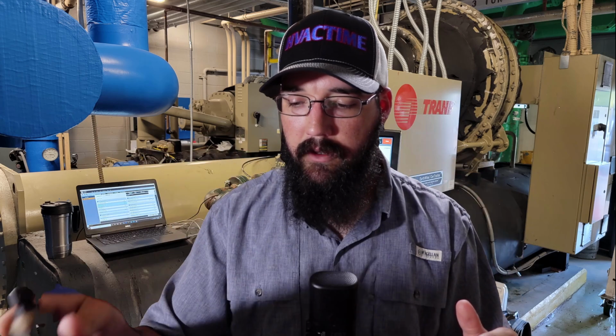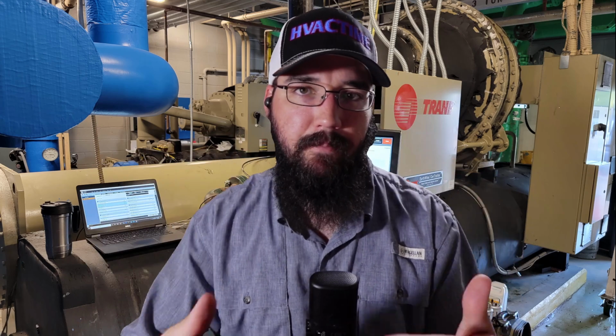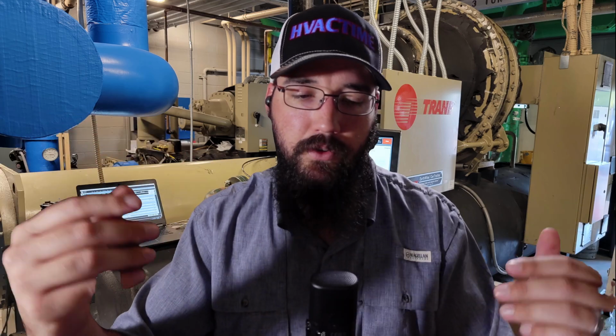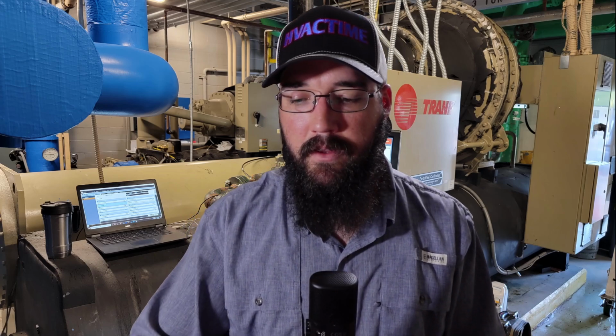Don't try to. I know with smaller valves, there are some on the market where you can do just the motor. Those ones you see on mini splits, as an example, the coil, the stator, is meant to slide off. It's just a ring that sits over it. That's not true for these larger valves. Electrical, mechanical failure, either way, that head is done. The body itself may be fine, but the head is done. I talked about earlier trying to take an electrical voltage reading. That is a method of trying to verify if you're getting power to the valve in pulsing, but you have to be very careful with that.